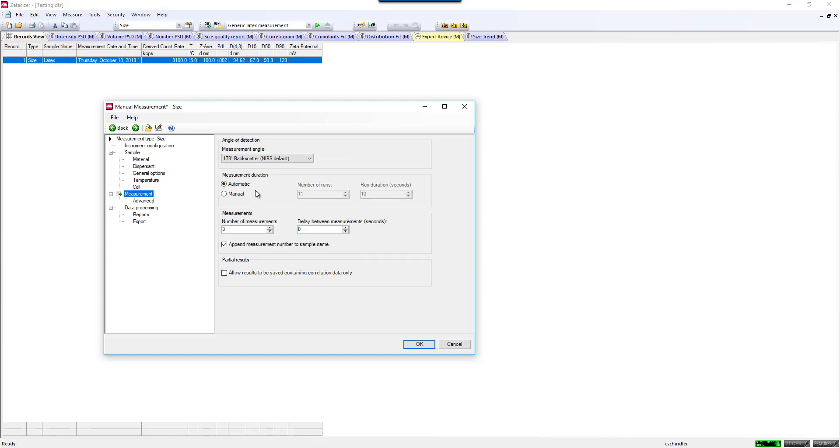On the measurement settings, a lot of the measurement settings you can select as automatic, so the instrument will adapt to your sample rather than you having to adapt and adjust the concentration of your sample to the instrument. You can select automatic settings, or if you're a more advanced user, you can use manual settings if you would like to compare two different samples to each other using the exact same settings.